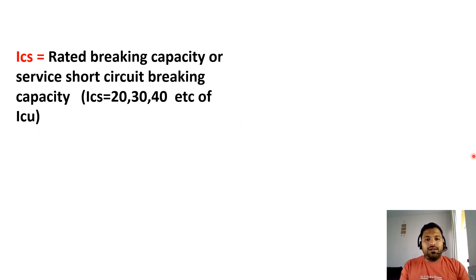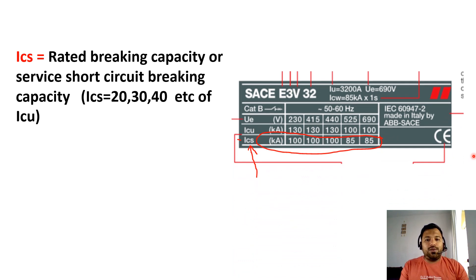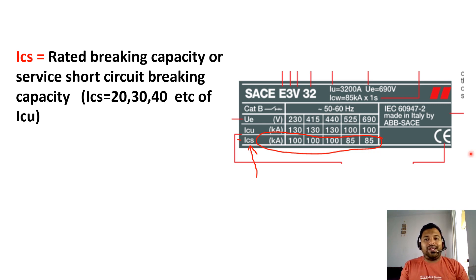If we look at where we can see these values — this is the ICS value. This means this breaker can interrupt fault currents of 85 kiloamperes, and in this case the circuit breaker will not get damaged. ICS value means the circuit breaker will not get damaged — it can withstand a maximum of 85 kiloamperes. This is what is written as the ICS value.